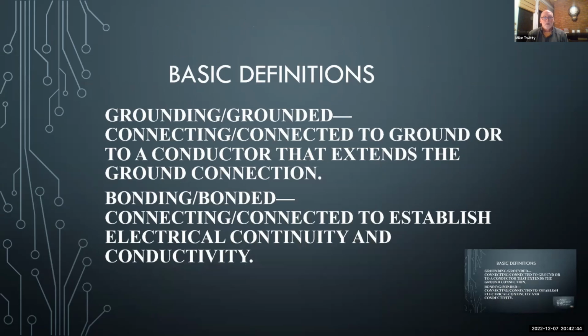Okay, here are some basic definitions. Grounding and grounded: that's connecting or connected. And these definitions actually come out of Article 100 of the National Electric Code. So I didn't write these; smart people wrote this, so we'll go by what they said. Grounding and grounded is connecting or connected to ground or to a conductor that extends the ground connection. Okay, that's kind of a complicated way of saying you're sticking something in the dirt and connecting to it.